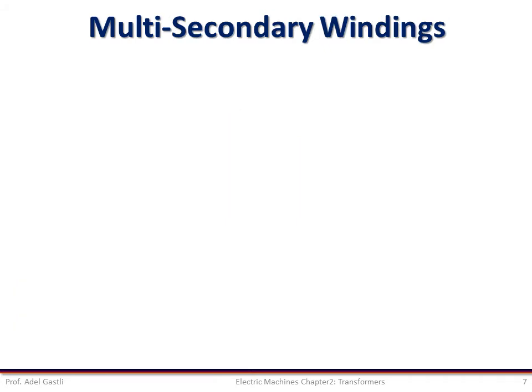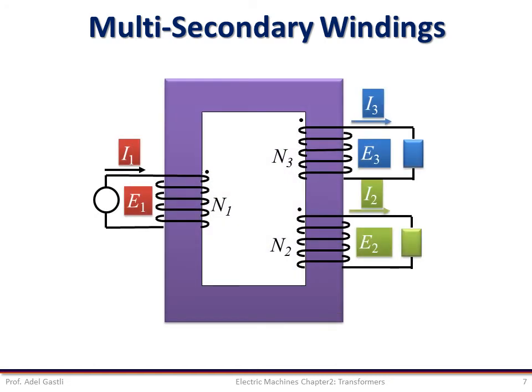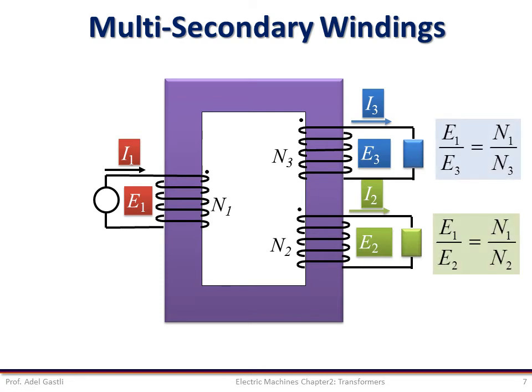We will see an example of multi-secondary winding transformers and describe its operation. Here we have one primary winding with N1 turns connected to the source, and two secondary windings: one with N2 turns and the second one with N3 turns. Each secondary winding is connected to a separate load and will have a different current depending on its EMF and the impedance of the load connected to it. From the previous two-winding analysis, we know that E1/E2 = N1/N2 and E1/E3 = N1/N3.